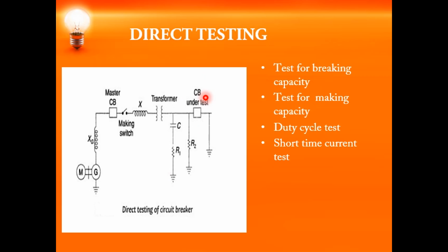Usually the short circuit tests which you carry out are the breaking capacity test, the test for making capacity, the duty cycle test and the short time current test. We will see them one by one. First, the testing for breaking capacity. First of all, you will see to it that the circuit breaker under test as well as the master circuit breaker contacts are both closed. The same testing procedure you have to follow: you close the make switch and the short circuit current is made to flow through the circuit breaker under test. So what has to be taken care of?